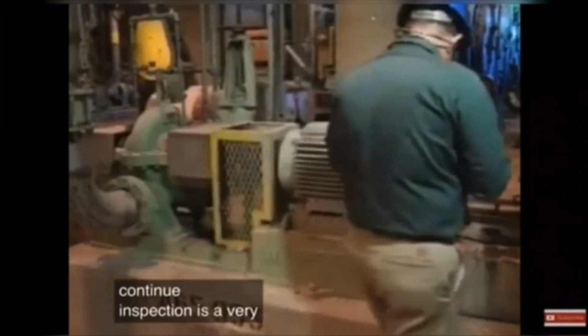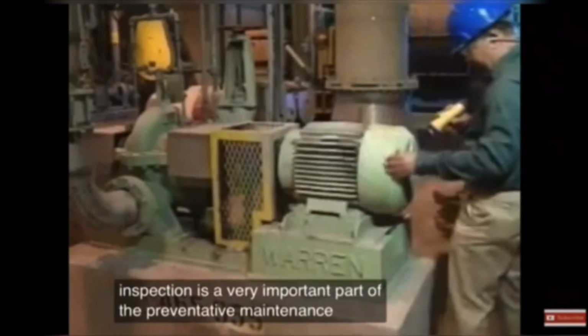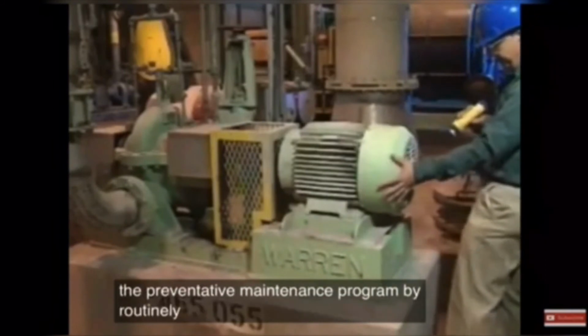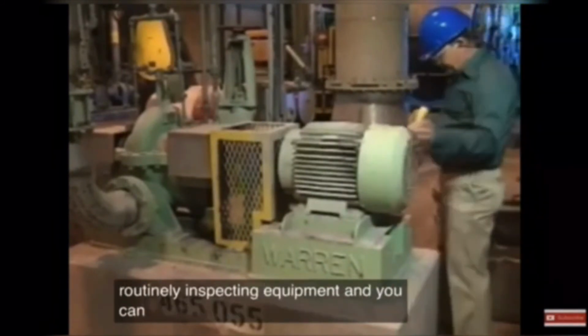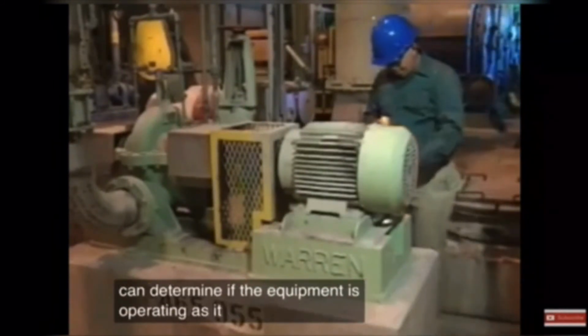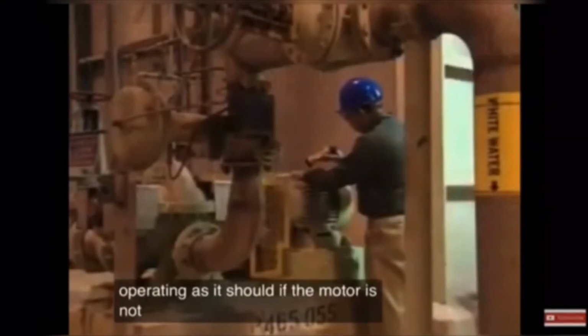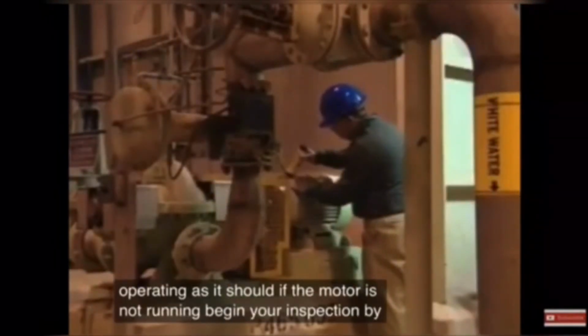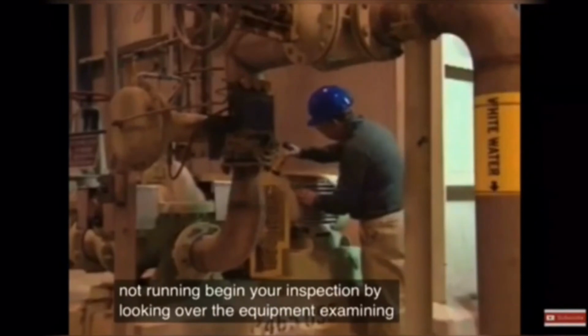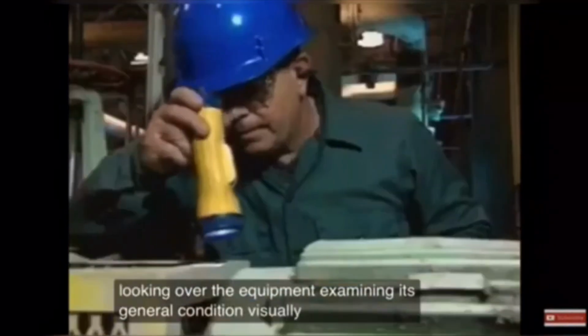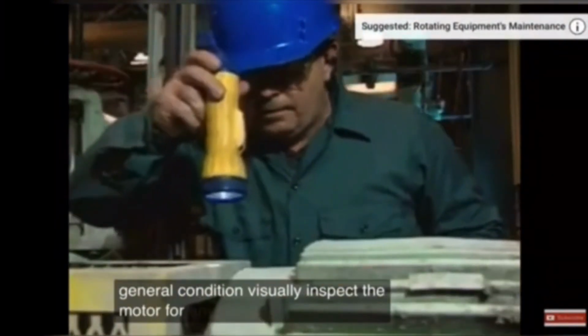Inspection is a very important part of the preventive maintenance program. By routinely inspecting equipment, you can determine if the equipment is operating as it should. If the motor is not running, begin your inspection by looking over the equipment, examining its general condition. Visually inspect the motor for any loose fastenings or broken parts.